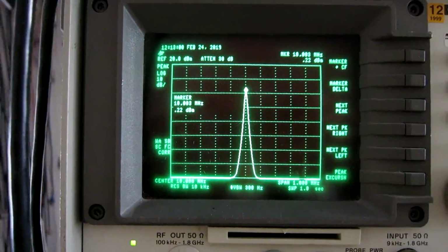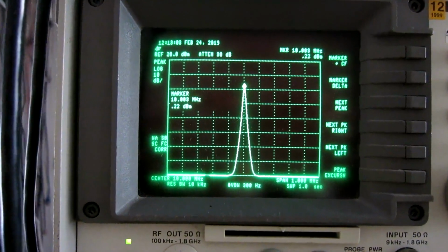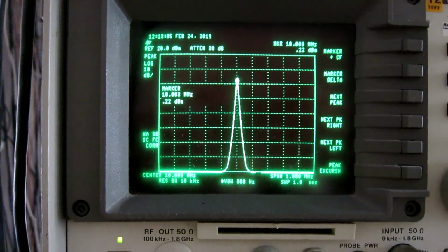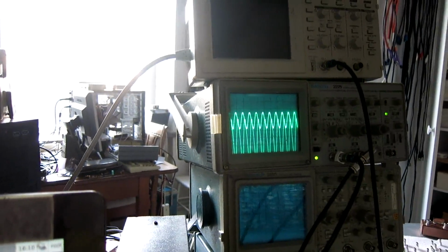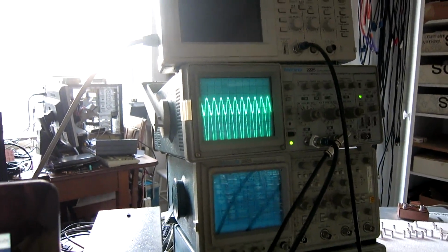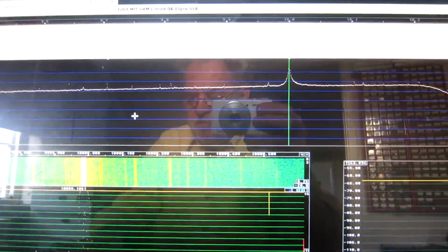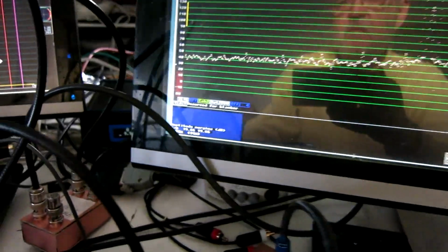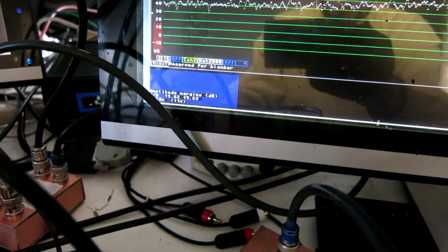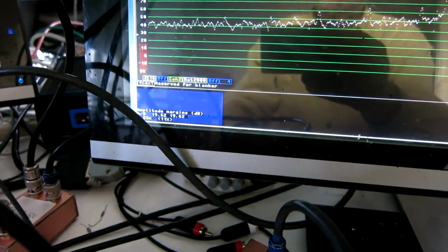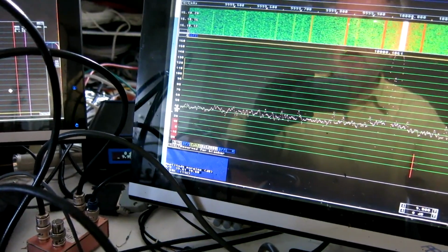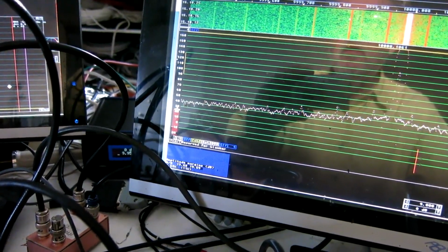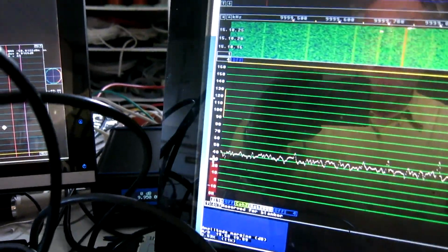Now I can look at close range, because that is more interesting for this kind of device. I have unbalanced the amplitudes to get a carrier that is reasonably strong in the interferometer. An amplitude margin now of 19 dB. Well, that is satisfactory with a good margin. And I want to send a little bit more on the network. I have to set the level here.